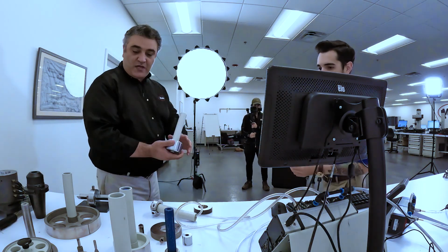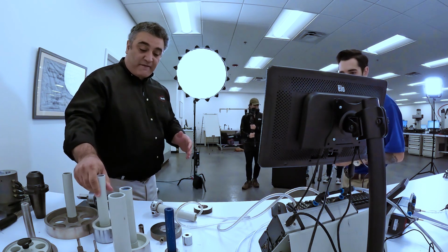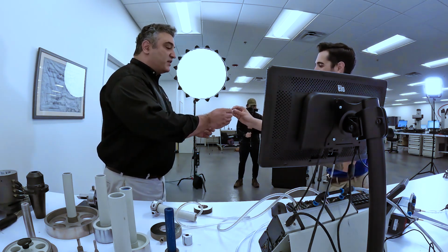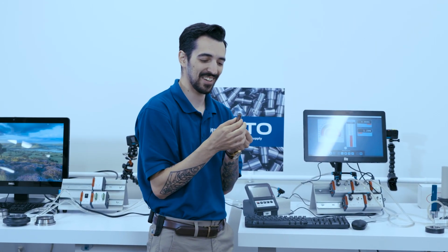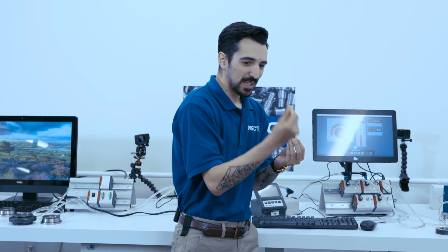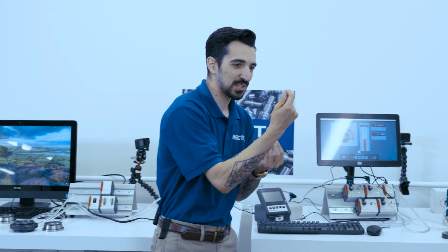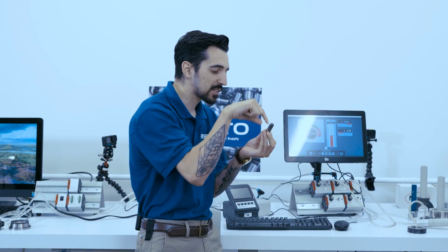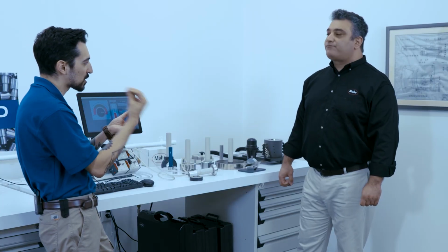That's sweet. And then we also have air plugs with more than 2 jets. These are 6 jets that will work for average diameter, for example. So is the increased number of jets similar to how, if I'm on a CMM or something and I'm adding points to check along my part, it increases your accuracy? Correct. Is that the same for you guys?